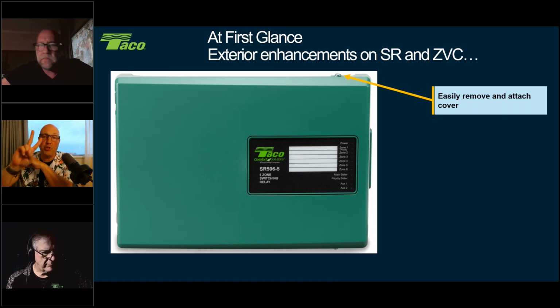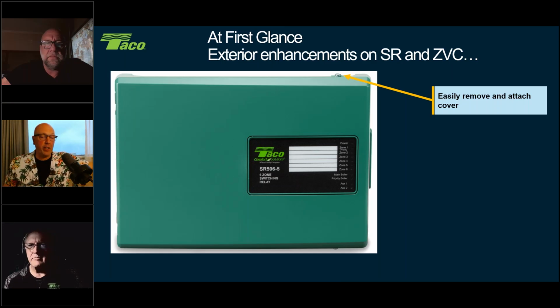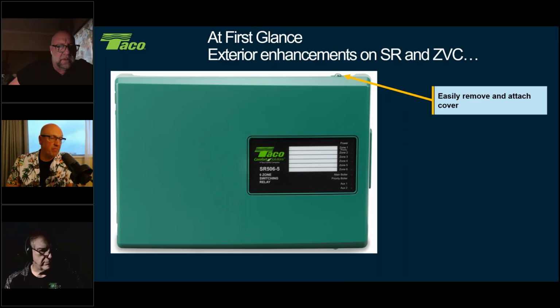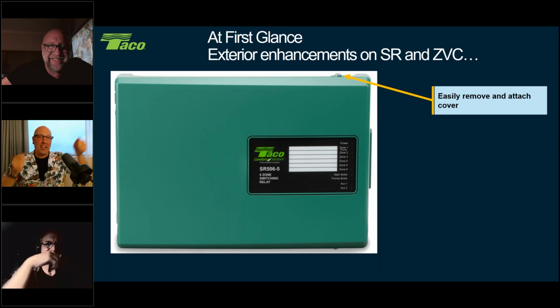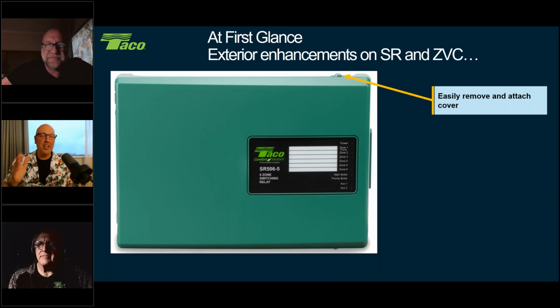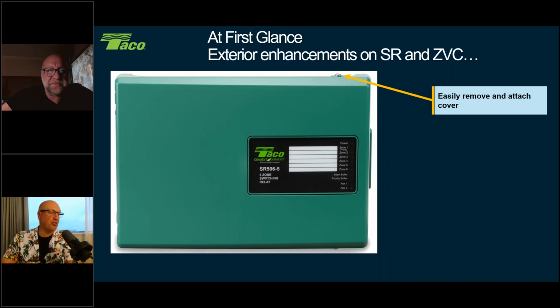The cover comes off with 2 screws and it's on a hinge. As soon as you loosen up those 2 screws, the cover lifts off to the left and comes completely off the board. So it's very clean, easy to take off. It's also a heck of a lot easier to put on. You line up the 2 tabs, you just drop the cover and it falls on the 2 screws. For those of you that have put in a Dash 4, have you ever gotten all 4 screws the same time the first time? You're always trying to line it up and you always miss one, right? So here you hook up the tabs and it just drops right onto the screws and lines up immediately.